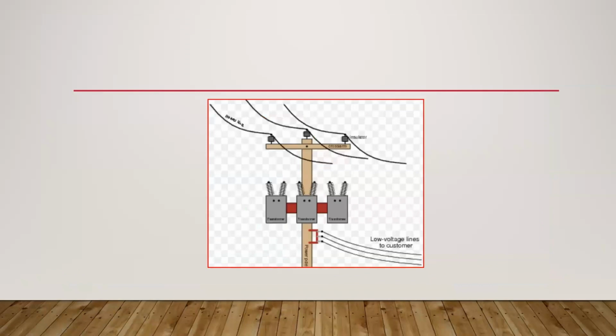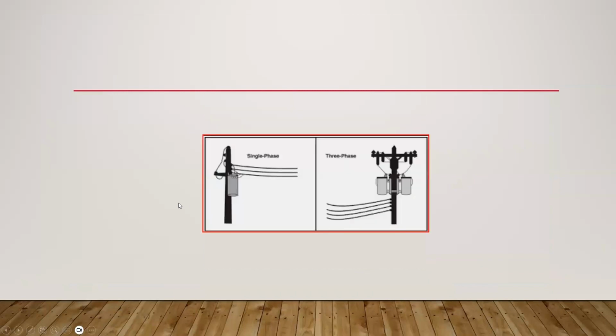What's happened over the years is that there are a lot of applications where the power company brought three power lines coming in from their source, dropping them through transformers and giving them full three-phase power directly to the motor. But there's also a lot of single phase out there where they put on one transformer, there's only 2 lines of power coming out, and then they have a ground neutral, so you have just 2 wires here.